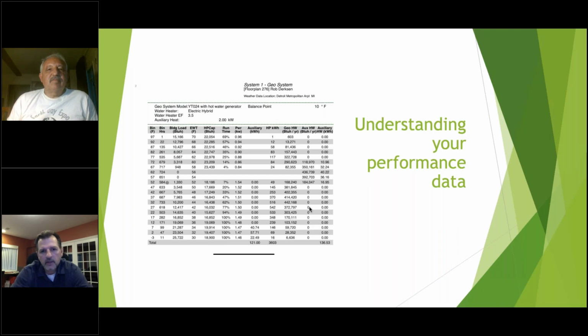We have a system here that would begin to use some auxiliary heat around 7 degrees above zero, and that would be considered a normal application here in the north, especially in Michigan. We'd like to have what we call a balance point of somewhere around 10 degrees or colder before we would expect or accept the use of auxiliary heat.